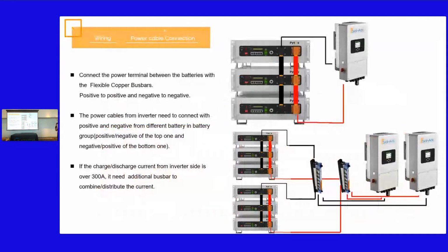Let's start with the installation process. The first step is to connect the power cable - connect the power terminal between the batteries with the flexible copper bus bar, then connect the power cable from battery to inverter. Note that if the discharging current from the inverter side is over 300 amps, you'll need to add an additional bus bar to combine or distribute the current.